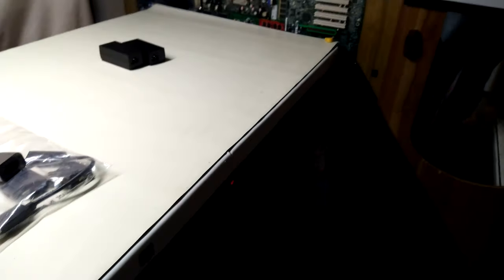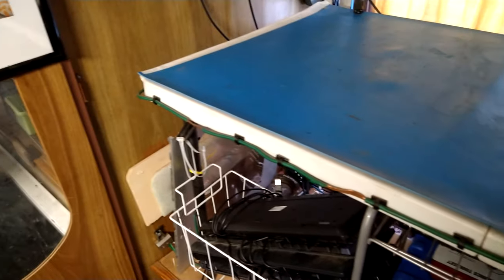I have ESD grounding. That goes to the metal frame of the trailer and to an 8-foot grounding rod outside, which all ties in over here, as well as a grounded floor mat. So I can wear wrist straps, or if you don't want to, jack into one of these little pre-stripped spots on the ground line.